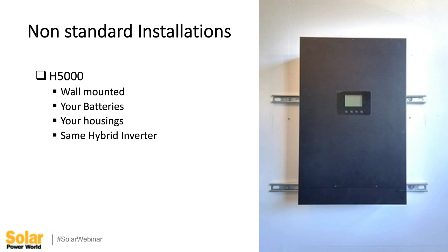Most string inverters correlate that 5,000 watts of output to how many watts of PV you can have. But remember, with a hybrid inverter you're doing multiple things—not only feeding back to the grid, but also potentially charging the batteries or providing power for the house under certain conditions. So you really need to look at both sides: how much PV you can attach, and how much power you can support. That's where the 5,000 is a really nice unit.